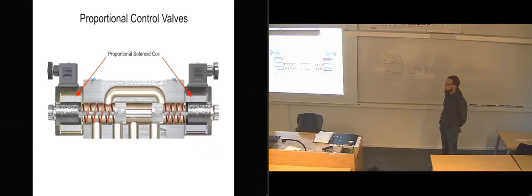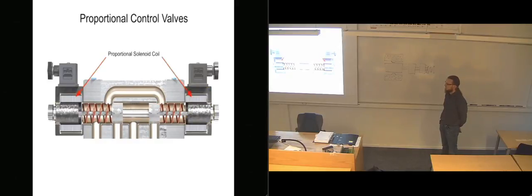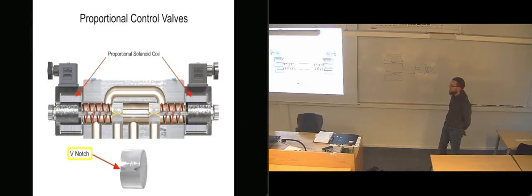As the internal valve spool changes position, new flow areas open up gradually and continue to open wider during full spool travel. To eliminate flow lag from spool overlap, most manufacturers cut V-notches that allow some flow to pass as soon as the spool moves.